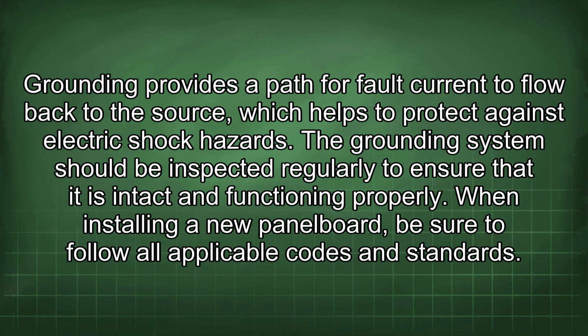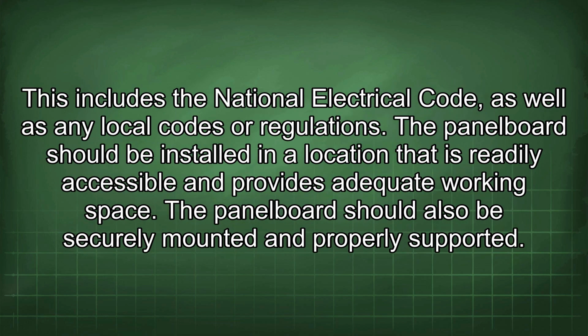When installing a new panel board, be sure to follow all applicable codes and standards. This includes the National Electrical Code, as well as any local codes or regulations. The panel board should be installed in a location that is readily accessible and provides adequate working space. The panel board should also be securely mounted and properly supported.